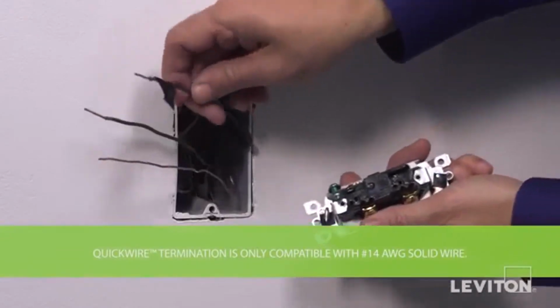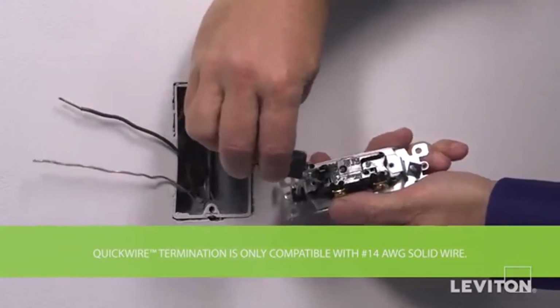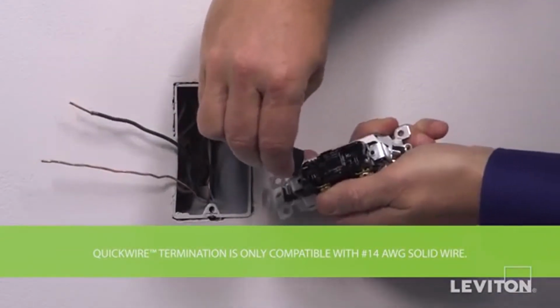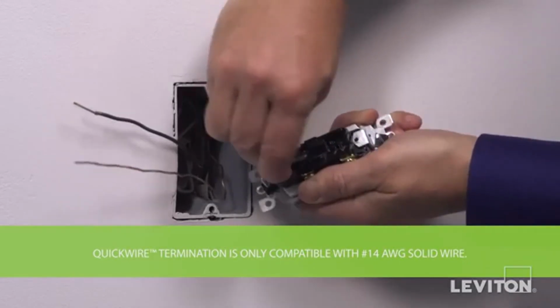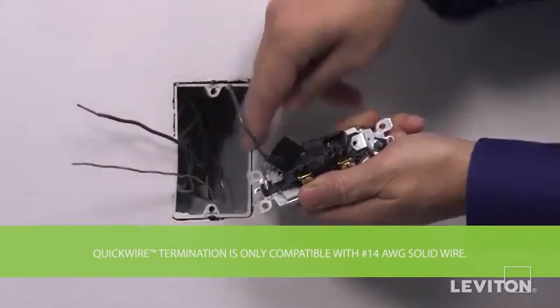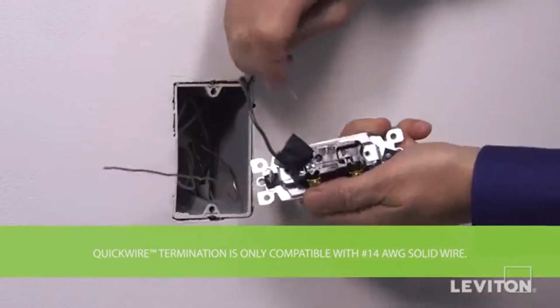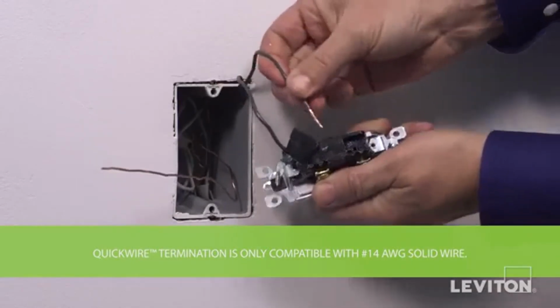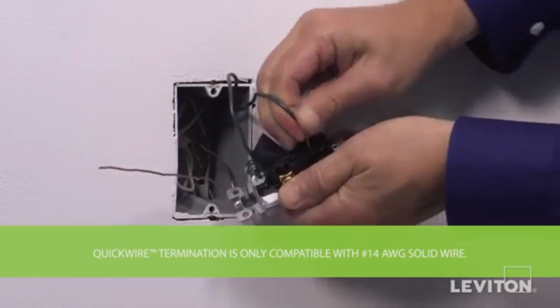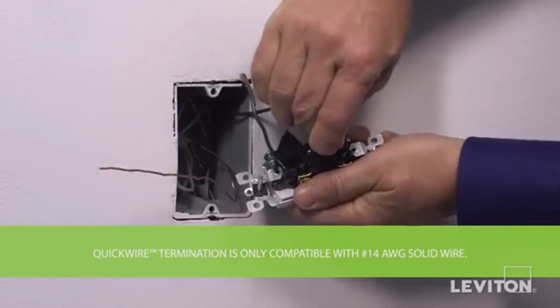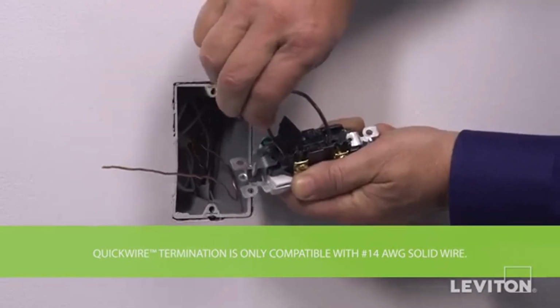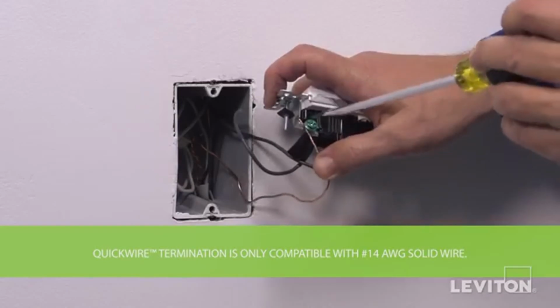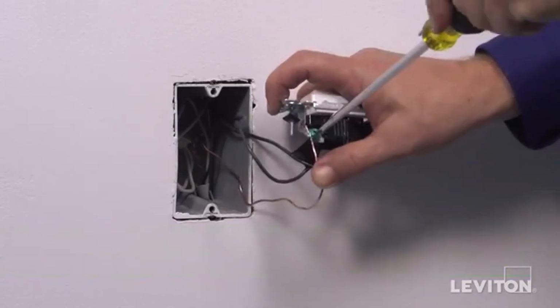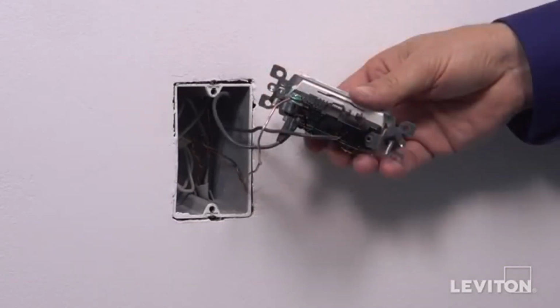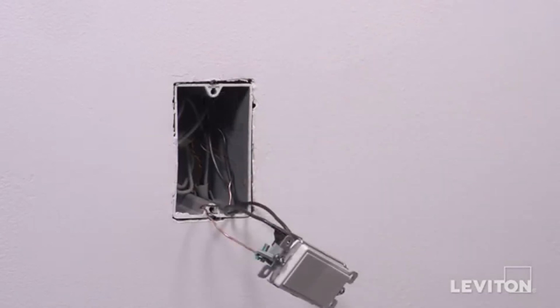These devices may also be quick-wired. To do this, insert straight 14-gauge solid copper wires into the round quick-wire holes located on the back of the device. Quick-wire terminals accept 14-gauge solid copper wires only. For circuits with 12-gauge solid copper or copper-clad wires, use terminal screws instead. The device is now terminated.